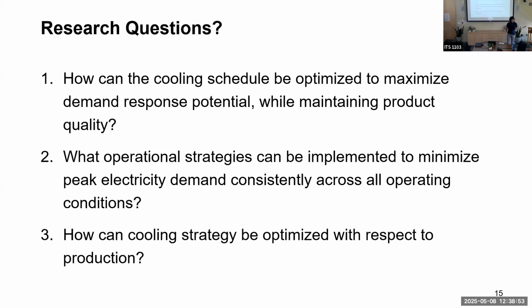And then what operational strategies can we adopt to reduce their overall demand, not just in the on-peak period, but throughout their operation? So if they're operating at a consistent load of 500 kW, what methods can we take to bring that down to 450, maybe 400? And those involve energy efficiency, obviously, and also how the system is operated. We can do some staggered operations, so not bringing everything online at once. We can start bringing compressors on one by one, coasting for a little bit.